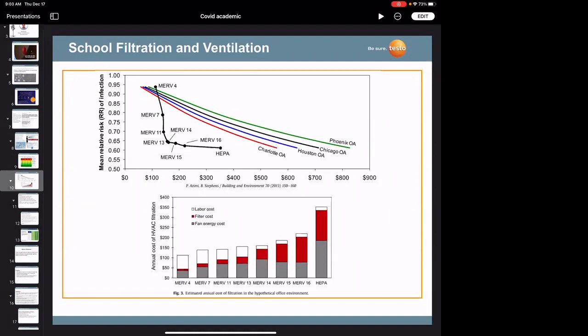So that's an important thing to recognize: filters aren't just straightforward like a sieve, like a spaghetti filter kind of thing. The other point I want to make, and get your reflection on, is that a lot of systems are designed to have a heating and cooling filter for space conditioning, but we're now talking about a new mode of ventilation filtration for health and safety, and the system might not be designed for it. That goes back to your point about being designed to do this. Perhaps something like bypass filtration, or taking a slipstream of the air and running it through a higher filter just for the sake of filtration only, might require redesign. What's your thought on that?